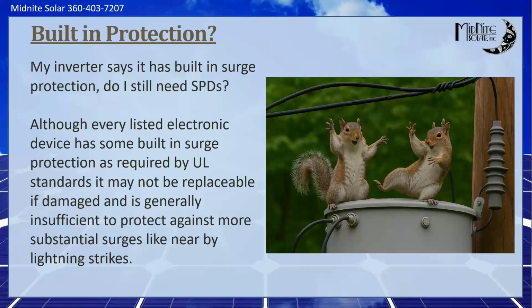So there are different reasons to add surge protection to an inverter that already says it has it, and it just depends on what the device is. But I always recommend external surge protection because it's going to take the brunt of the work and save the electronics. And again, even if you've got a Midnite all-in-one and you can replace the MOV board in it, you still have to tear the inverter apart to do that. It's not hard, but it's not super easy. Whereas with a surge arrestor, you can unhook the 3 wires, spin the wing nut off, put the new one in, hook the 3 wires back up, and you're back in business.